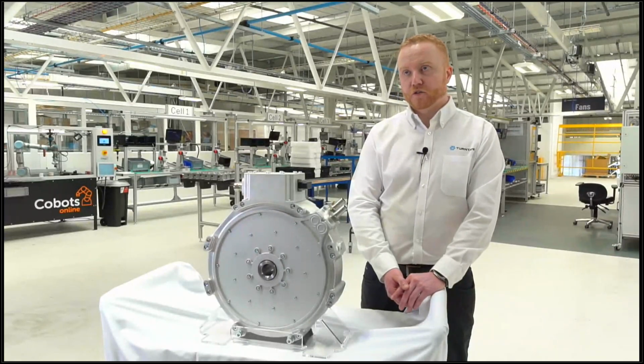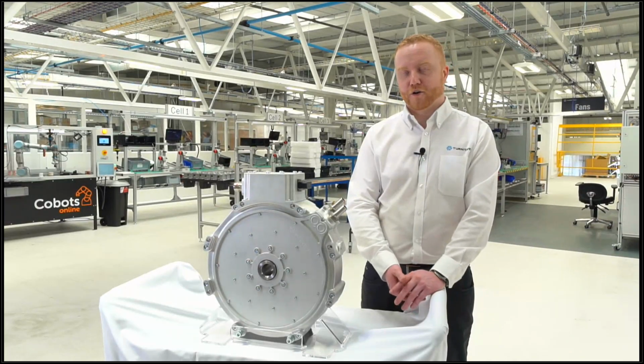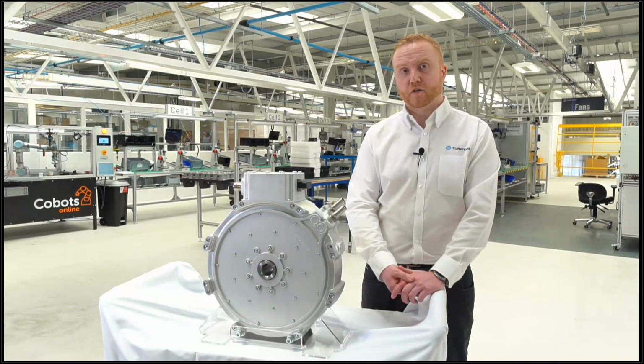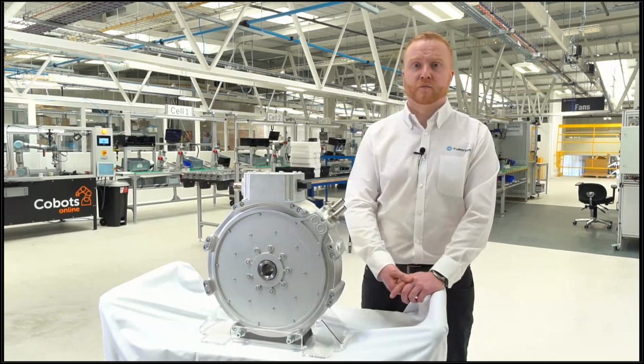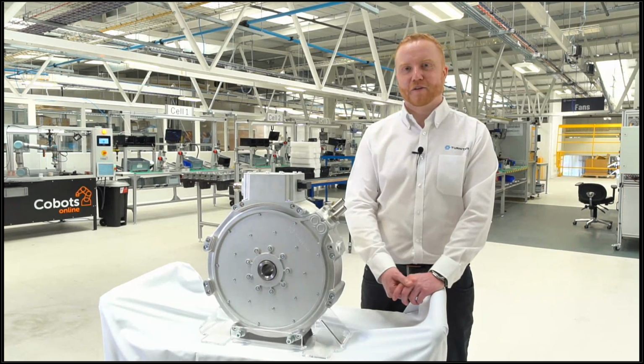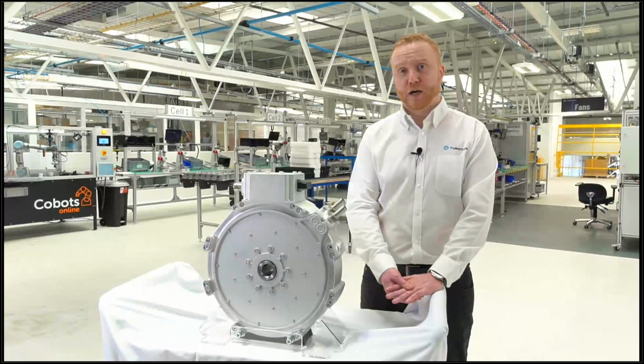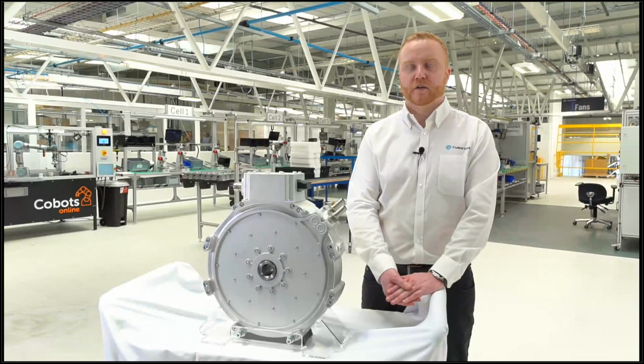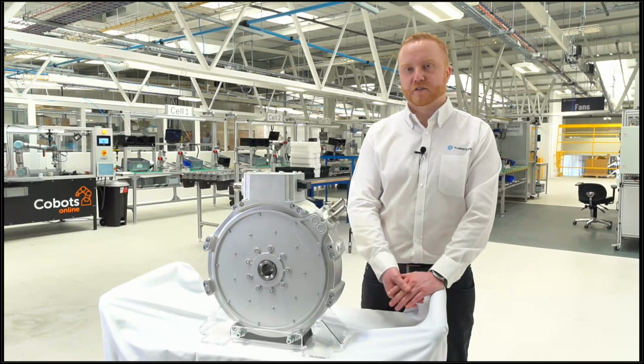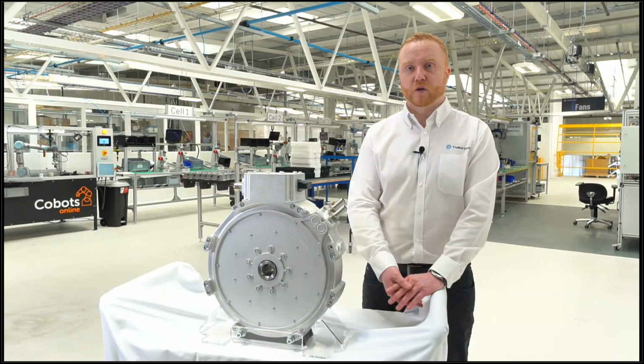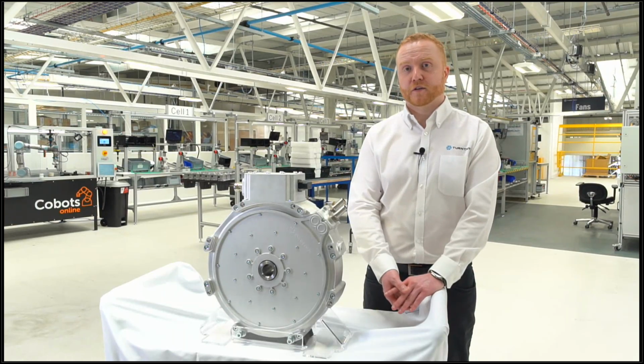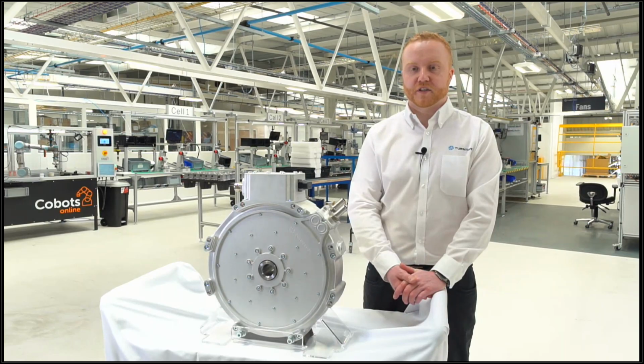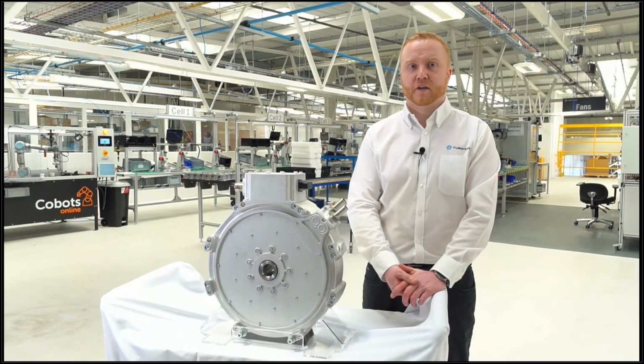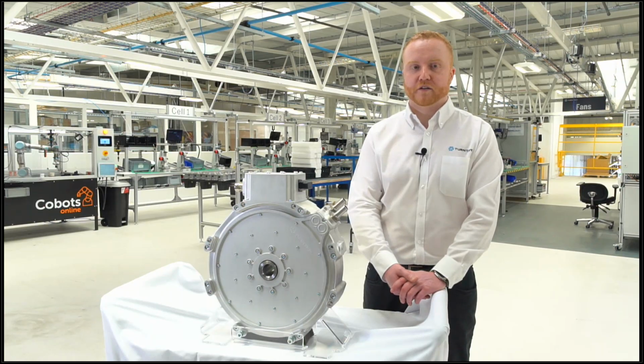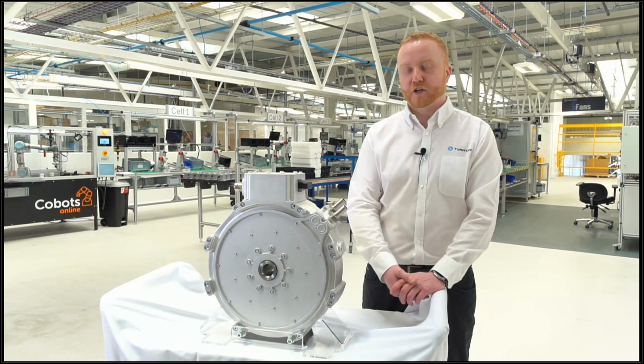I think this question might mean regarding alternative fluids for cooling — please correct me in the comments if I'm wrong — but we see a number of customers currently engaging who are using alternative liquids, such as oil or dielectric fluid. Similar to my other answer, it comes down to the specific detail, but generally we've seen other customers use other fluids to indirectly cool the product. Typically with these different fluids, you may have a difference in specific heat capacity and density, which can affect cooling behavior, so you may see a drop in performance. But if you haven't got water ethylene glycol in these systems, it can be worth taking that slight reduction in performance rather than integrating another system. So yes, we can accommodate different fluids, and we'd be keen to work through that and understand what our machine can deliver in those systems.